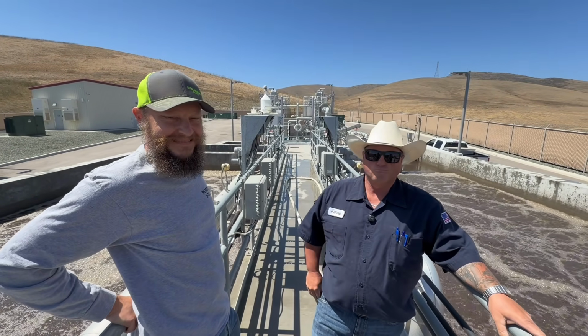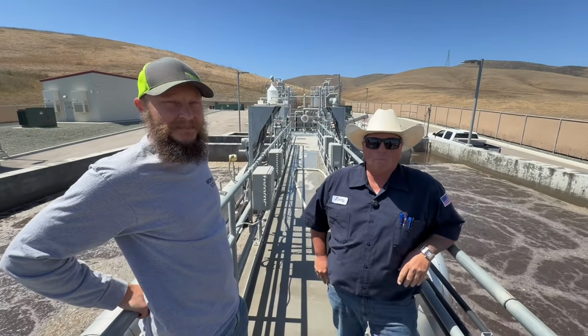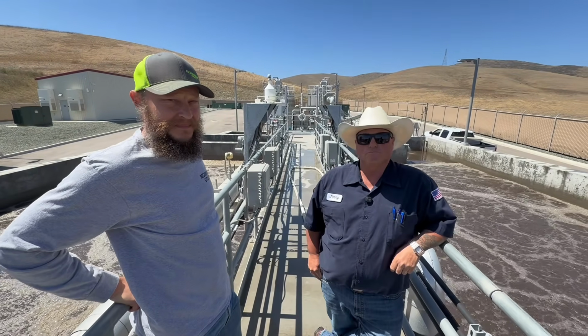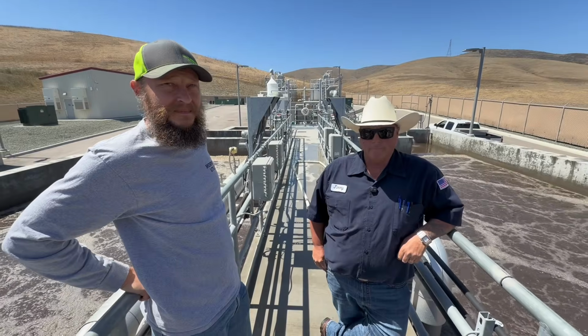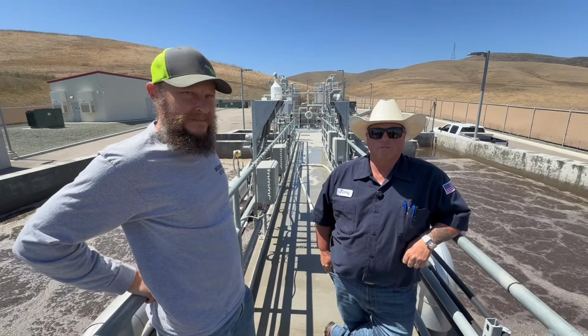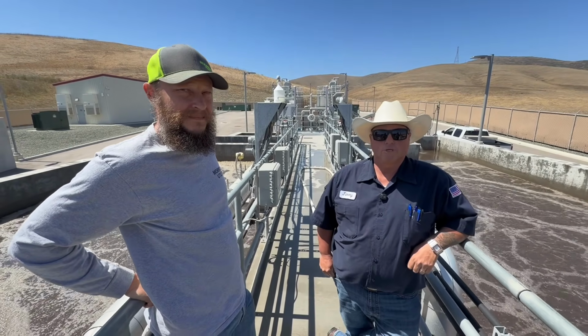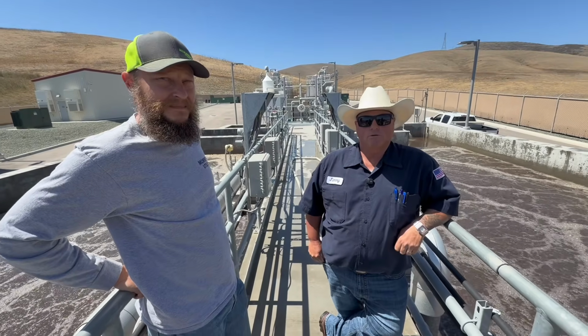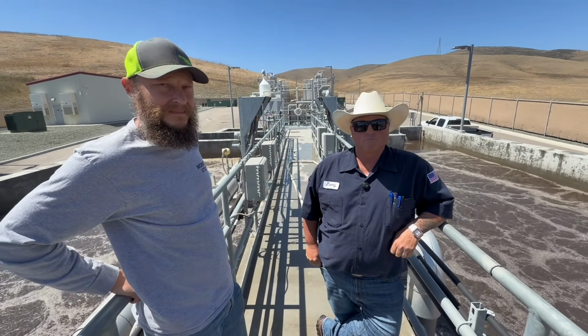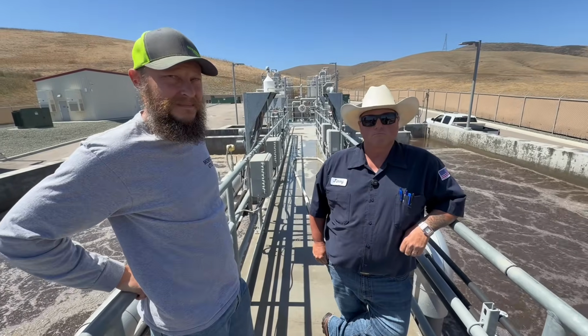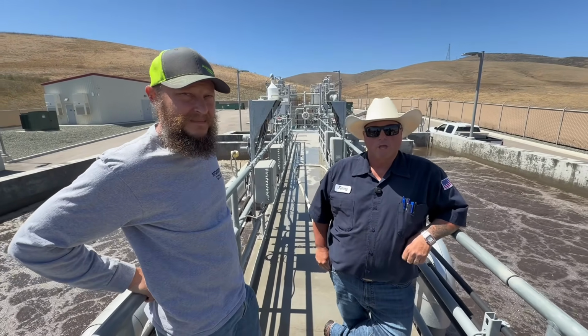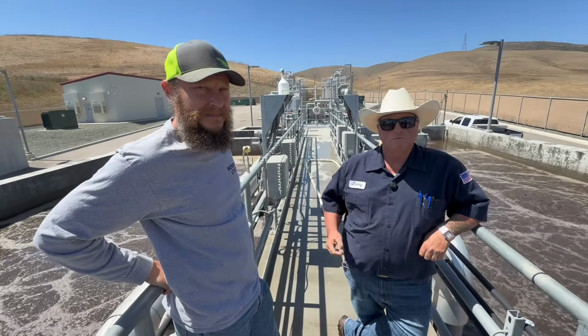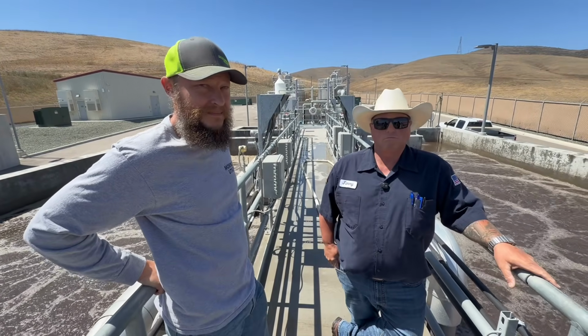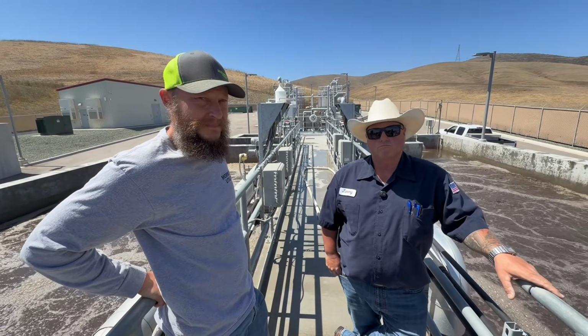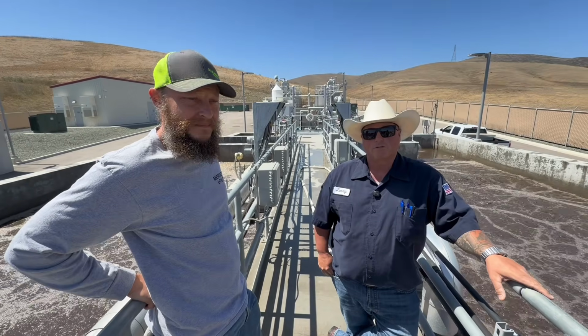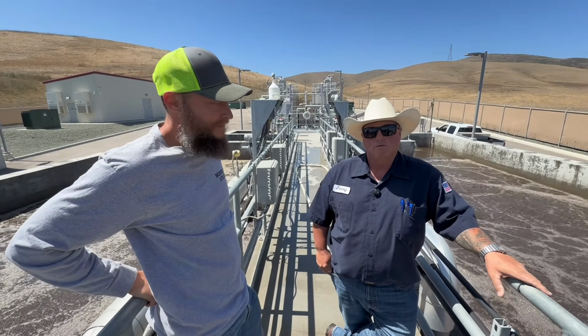Yeah, so it really is a testament to have an operator walk by and tell that to us, because that's something I see on a daily basis, the feedback loop, the blowers ramping up and down because I want 2 milligrams a liter in aeration right now, or I need negative 50 millivolts in my ORP in anoxic, and I need to have that feedback so I know, and like you just said, Grant, it needs to be correct. So, correct information. So I know, do I need to lower dissolved oxygen? Do I need to lower return? Like, what's going on? Why is my ORP drifting higher or lower, right?